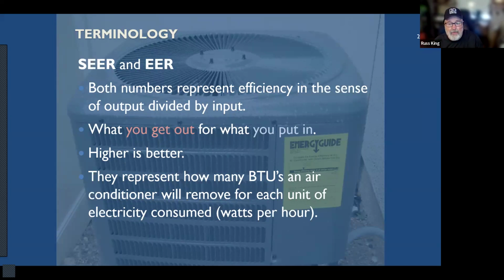You get BTUs per hour out. All right. And then that ultimately boils down to watts. How many watts are you putting into this air conditioner per hour in order to get a certain amount of cooling out? Okay, but SEER and EER, they're unitless. They're unitless numbers.